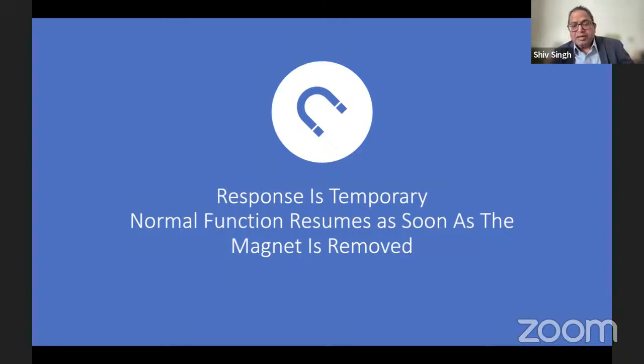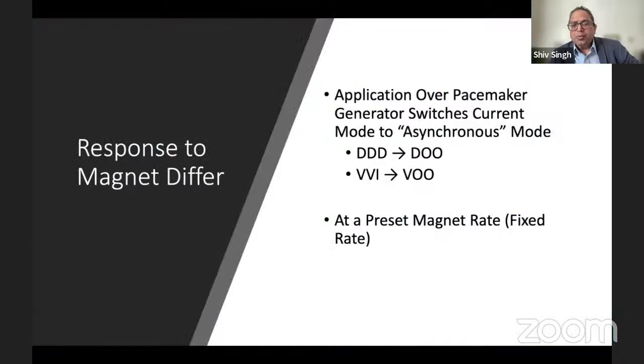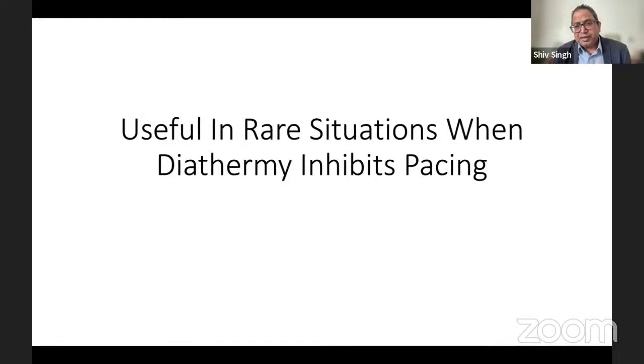So when you put a magnet on the pacemaker unit, a DDD is changed into a fixed mode, DOO, or VVI to VOO, at a preset magnet rate. Now the magnets were used to check battery life. So if the pacemaker unit is set to have a fixed rate of 85 per minute, but when you apply the magnet it's only pacing at 60 beats per minute, that means the battery needs to be changed.